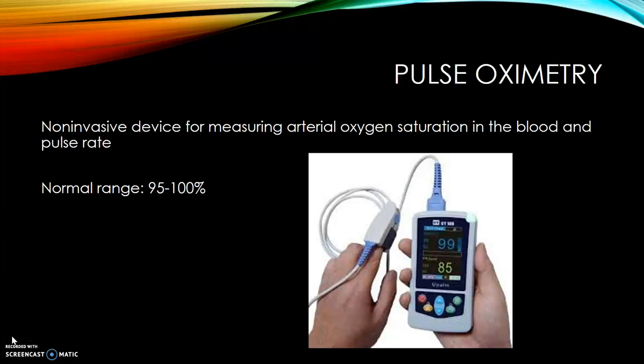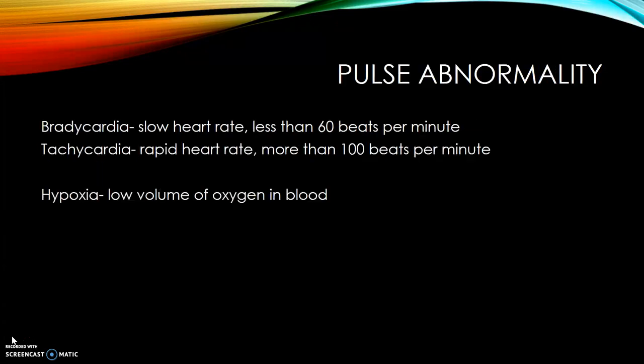Pulse oximetry is a non-invasive device for measuring arterial oxygen saturation in the blood and pulse rate. The normal range is 95 to 100%. Pulse abnormalities include bradycardia, which is a slow heart rate or less than 60 beats per minute; tachycardia, which is a rapid heart rate of more than 100 beats per minute; and hypoxia, which is a low volume of oxygen in the blood.